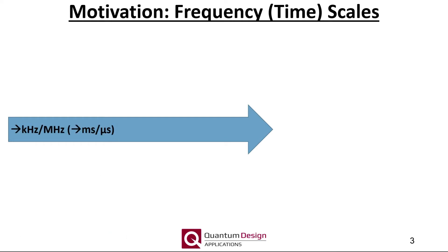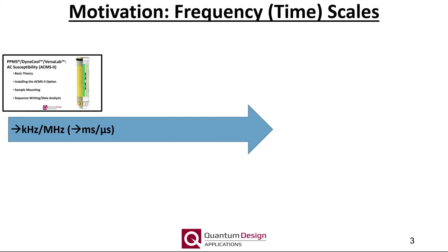As the excitation magnetic field frequency increases, we enter the realm of what is typically referred to as an AC susceptibility measurement. In an AC susceptibility measurement, we are interested in how the magnetic moment vector responds to an AC field. For example, the AC-MS2 PPMS option operates up to 10 kHz and is discussed at length in our AC-MS2 webinar, also found on YouTube. AC susceptibility measurements have found great utility in the study of spin glasses, superparamagnetic nanoparticles, and of course, superconductors. Note, while not offered for the PPMS product line, AC susceptibility measurements can be performed well into the megahertz range.